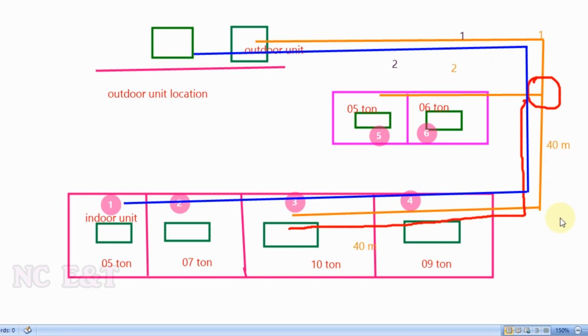Now the next stage is to total the tonnage of the indoor units. For circuit 1, we sum the tonnage of rooms 3, 4, 5 and 6, which gives a total of 30 ton. So we will select an outdoor unit of 30 ton for circuit number 1. In the same way, for circuit number 2, the sum of 5 plus 7 is 12, so we will select an outdoor unit of 12 ton for circuit number 2.